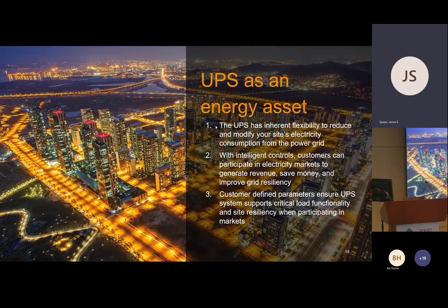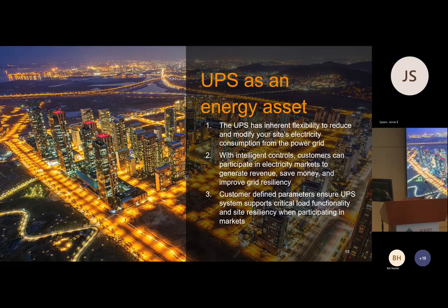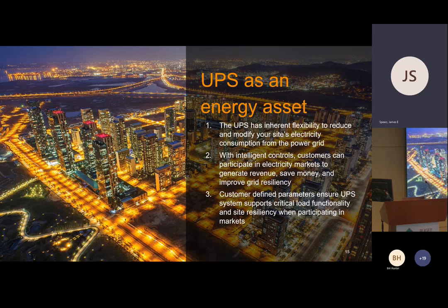A UPS system, by its nature and design, has the flexibility to modify your site's electricity consumption from the grid. How does it do that? Well, in general, a UPS system is loaded less than 50% of its capacity. Maybe that's because it's part of a redundant system, or because the headroom in the design only allowed for about 50% or 40% loading. But it's very common to have a UPS loaded at 50% or less.